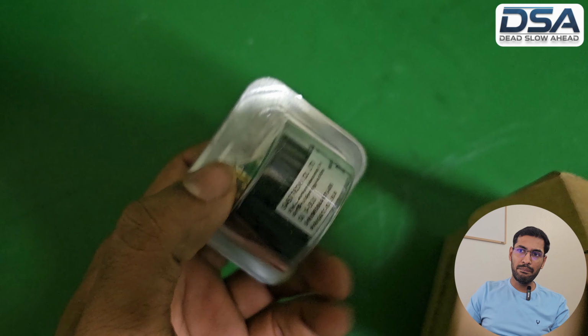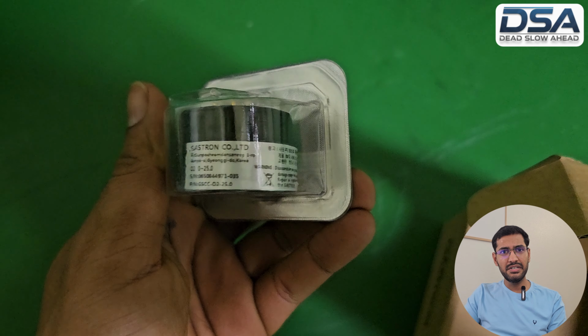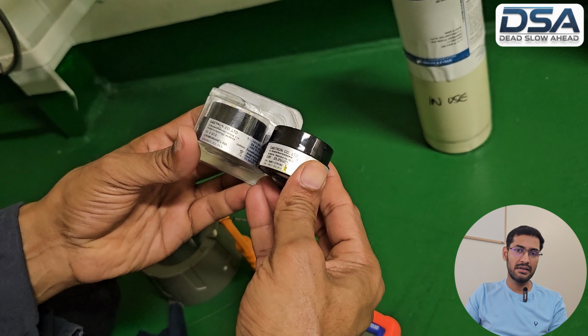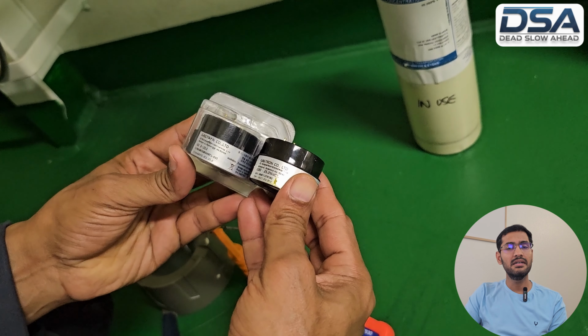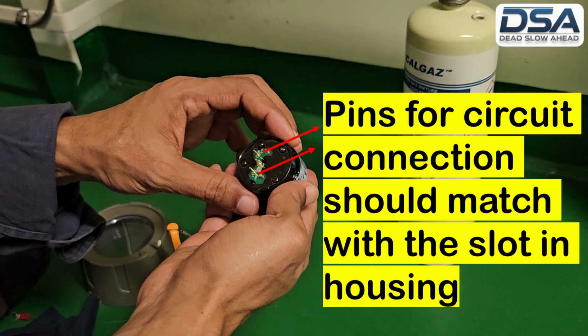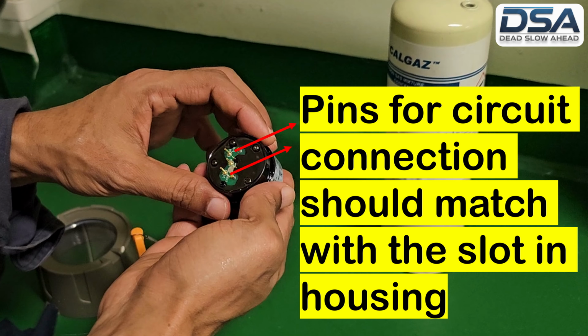So here is the new replacement sensor, and before installation you need to ensure that it matches the same model number and the same version number. Although this sensor has come from the same maker, sometimes they might have updated the version number. Because of the terminal and pin alignment of the sensor, as you can see, even a small difference in model number or version number can lead to improper fit or improper reading. So this step is very important.